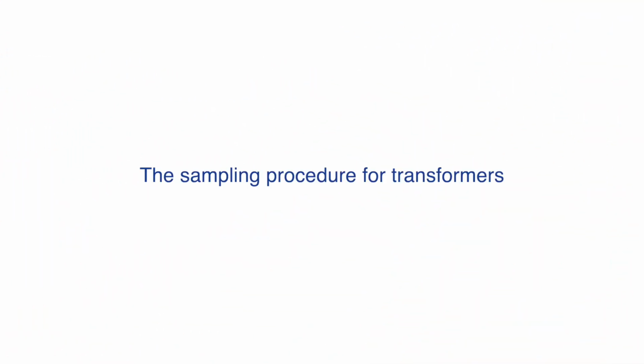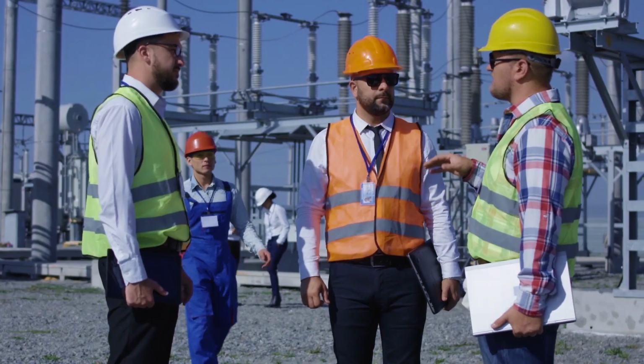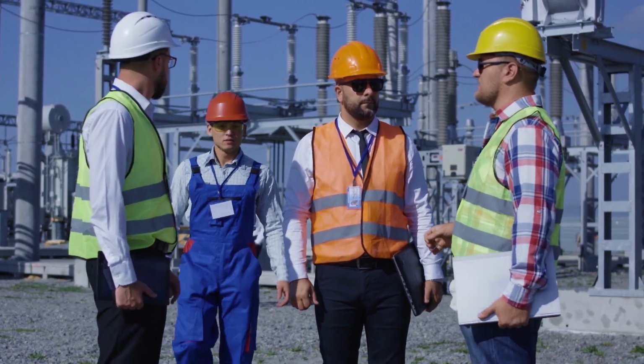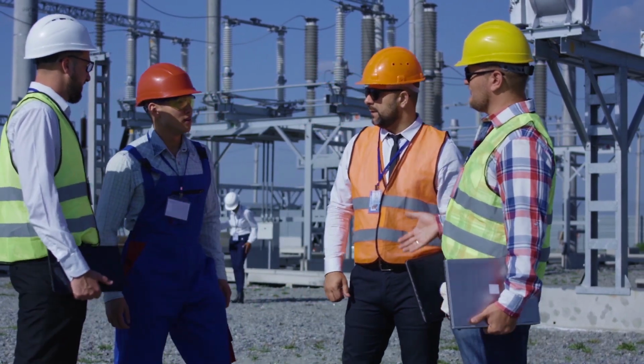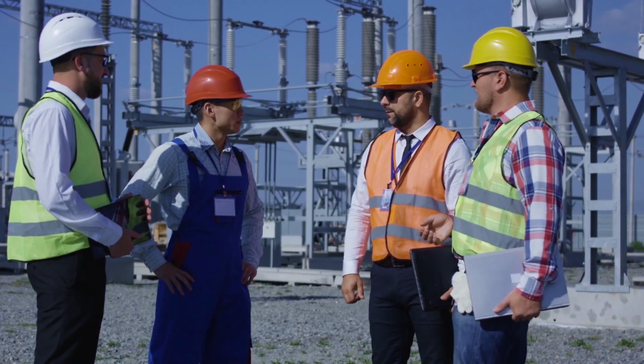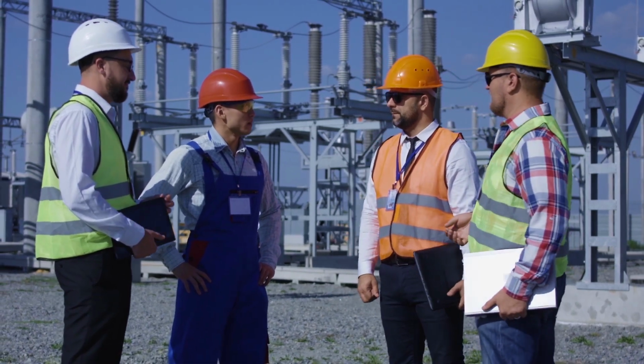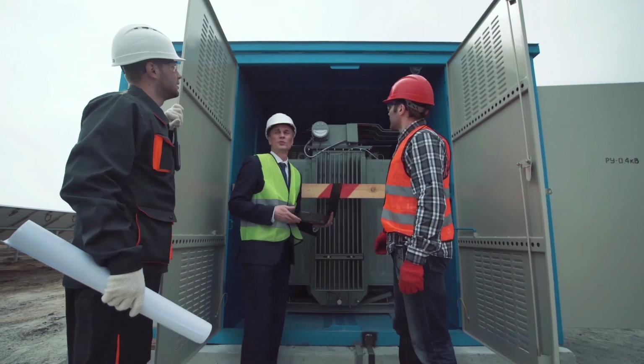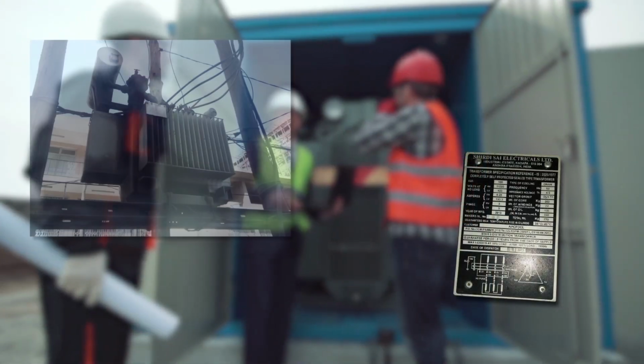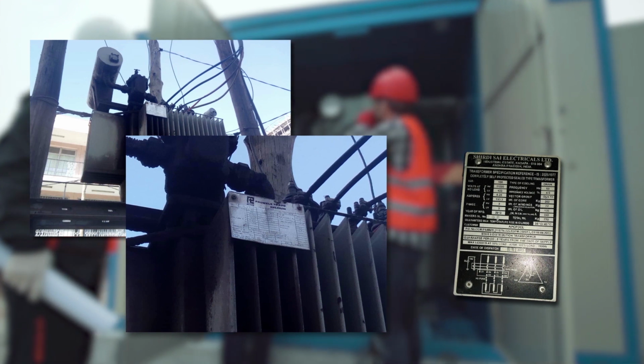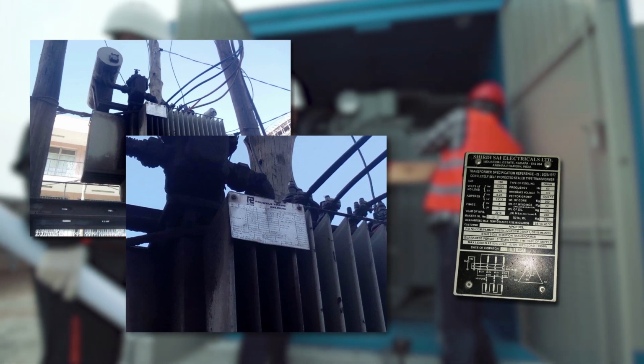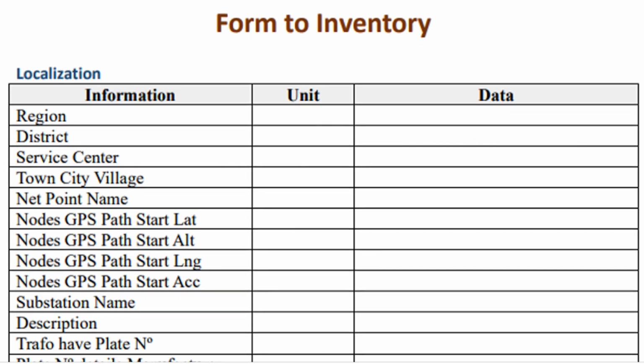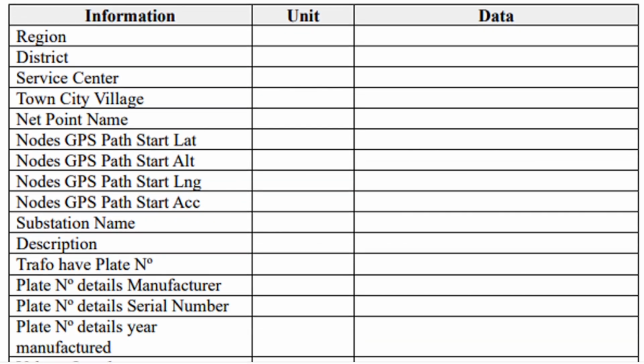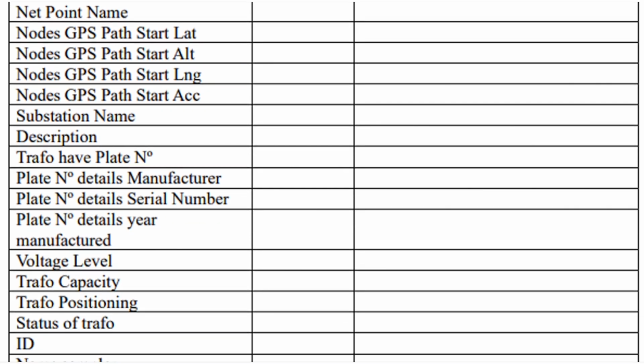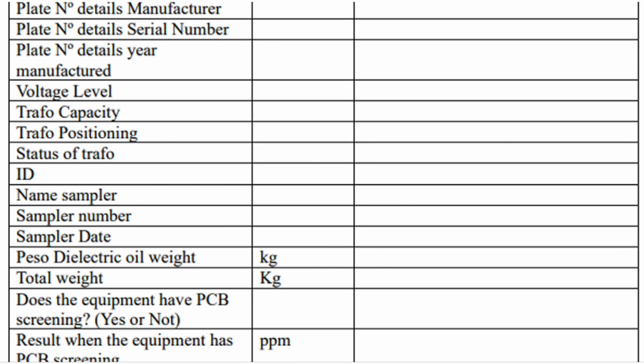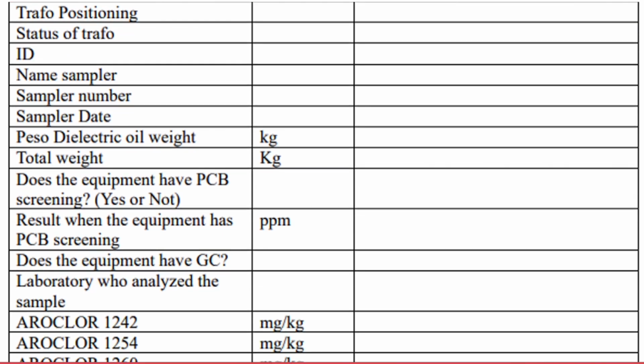The sampling procedure for transformers. Before the sampling starts, the sampling procedure, safety, and emergency measures are to be reviewed during a preliminary meeting. All measures must be discussed within the team, and responsibilities assigned and clearly understood by team members. Prior to sampling, the manufacturer plates should be located on each transformer, and the information, together with information on the location of the equipment, is to be filled in the inventory form. If the manufacturer plate is missing or not legible, the team should collect other information that can be used to identify the transformer, or assign it a unique number, in order to identify the equipment during the inventory.